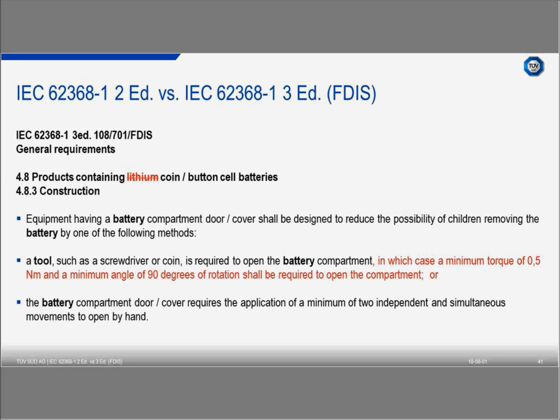The other topic that was updated is that you need 2 independent movements for opening the battery latch, and this is now clarified: the test is with a minimum torque of 0.5 Newton meters and a movement of 90 degrees. That's now clarified as a requirement in this area.